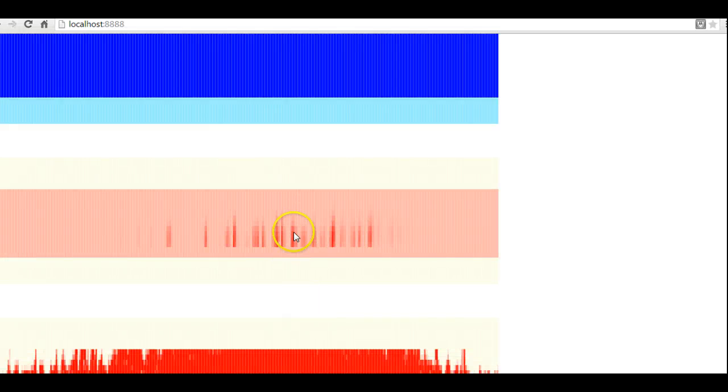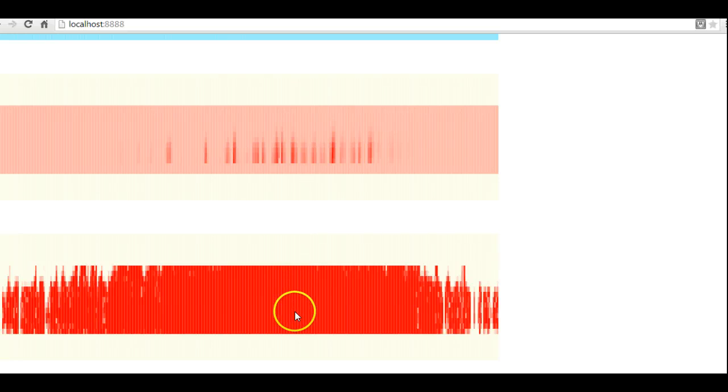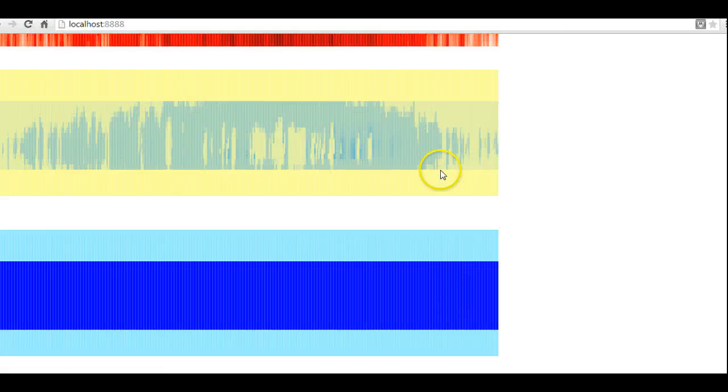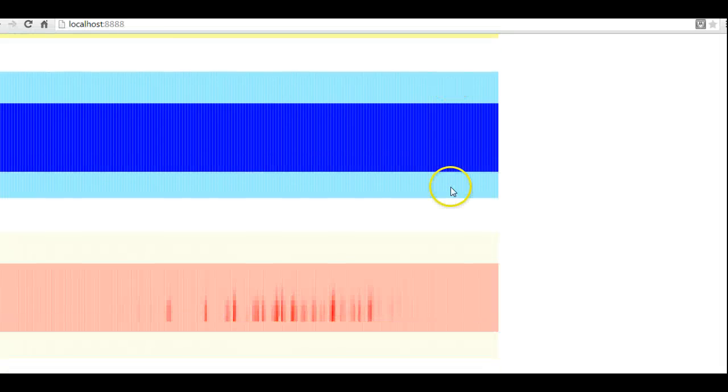And that correlates pretty well with when fan energy is high. And well, this isn't a great scale, but it also seems to correlate pretty well. At least you can see where the scale is a little bit better for cooling, how the economizer is responding as well.